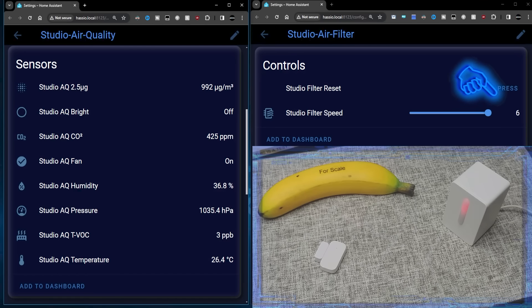I'm going to demonstrate how the particle count governs the speed of the air filter. So first, I've got a little smoke machine here. I'm going to put some smoke in the air and we'll watch the particle count go up. As you can see, the particle count has gone right up. And because it's over our 400 max threshold, that fan speed is now speed 6.